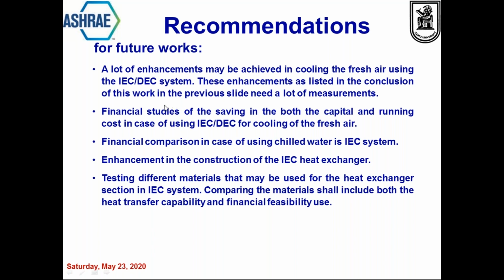So for our future work, with these recommendations, we are doing financial investigations to look into the savings in both the capital and running cost of the system, because we have the pumps for the sprayed water, and we have the energy for the humidifiers, and we have the power for the fans, and all these have to be considered in your life cycle cost analysis. Testing different materials that can be used for the indirect evaporative cooling is very important. We have to look into the heat transfer capabilities and also the financial feasibility of using these systems.